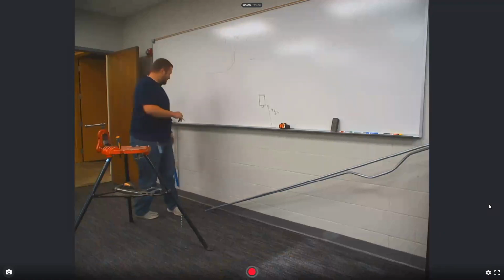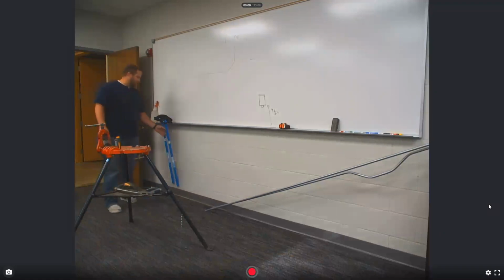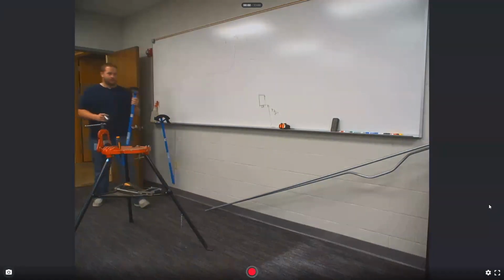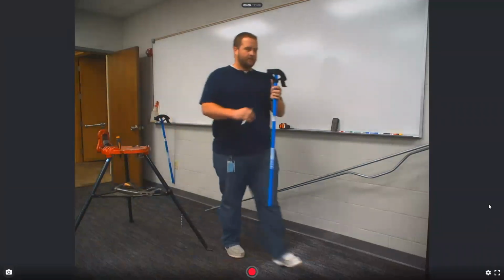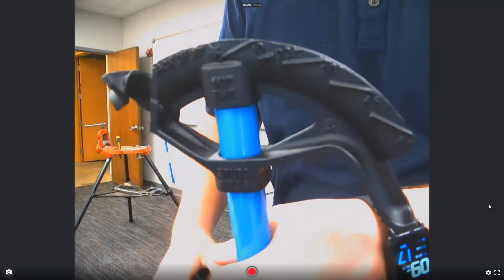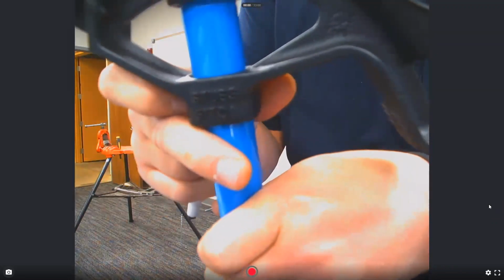It always has to do with the radius of the bender that you're using. On hand benders, there's a standard. For a 1/2 inch EMT, the take up is 5 inches. And for a 3/4 inch EMT, the take up is 6 inches. And most good benders will say that on there somewhere. This one says stubs 5 inch to the arrow. Right here. Stubs 5 inches to arrow.